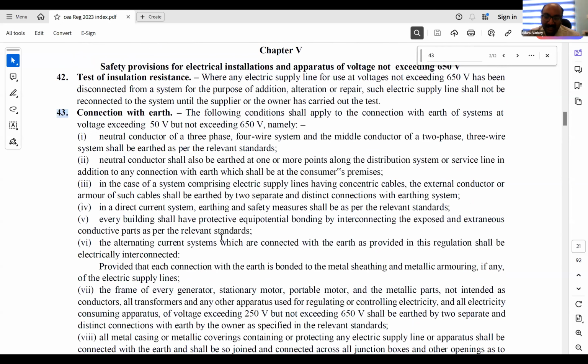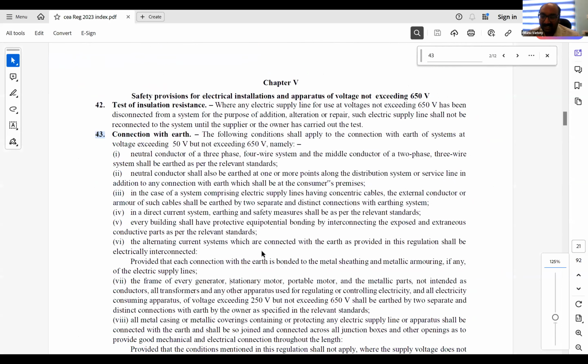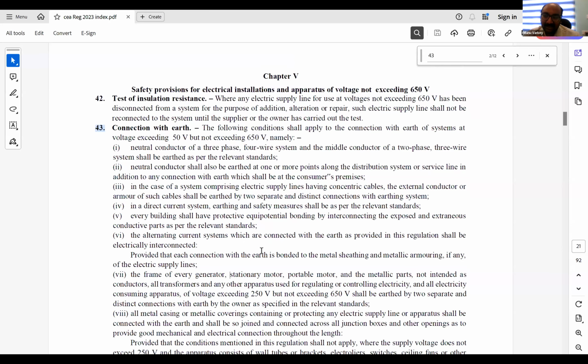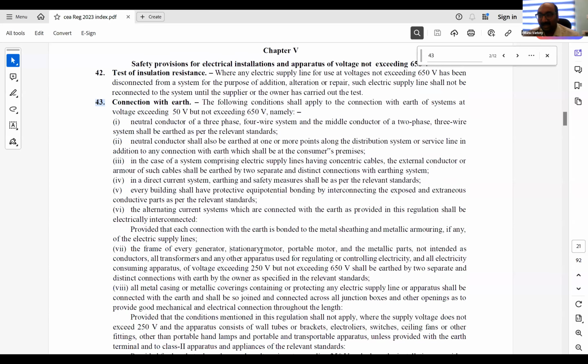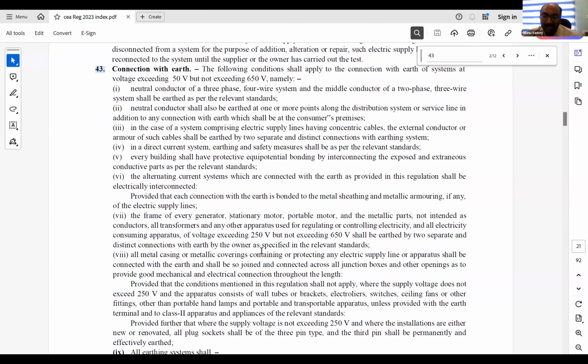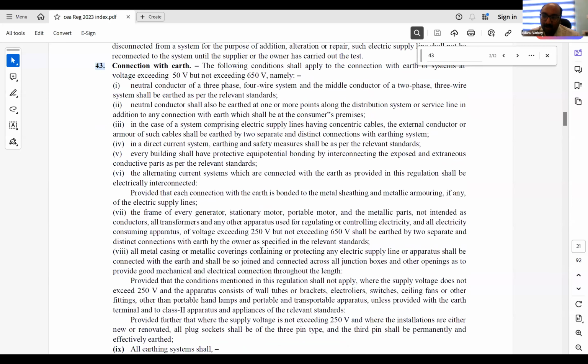So the earth electrode has less of a role to play on the LT side. Here the role of the earth electrode is limited to referencing the system to ground. But the fault protection is handled by having a lower loop impedance.